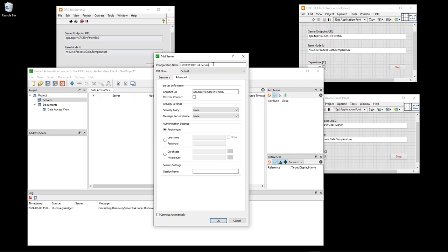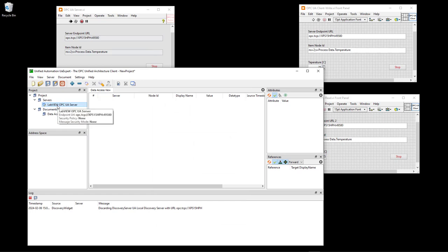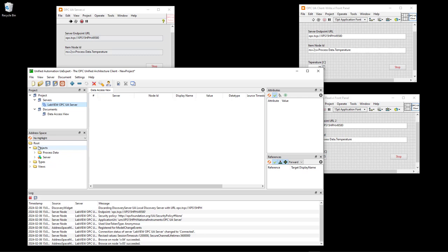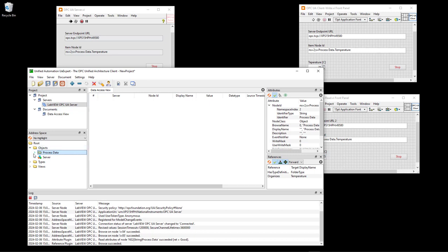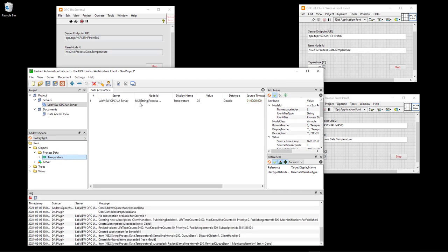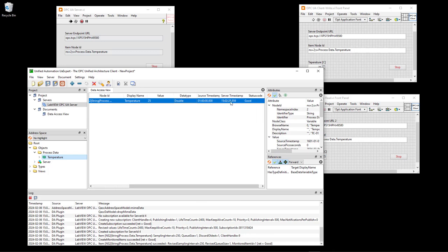This is the name you can specify for your server and this is the endpoint URL for this specific server. Then just click OK and the server pops up here in the list. You can right click on it and click connect in order to connect to that server. When you are connected, you are able to see the tags that are part of this server. Here you find the same process data, and here you find the temperature tag. You can see the data type, timestamp, quality, node ID, etc.